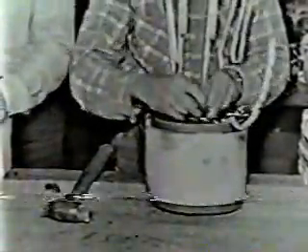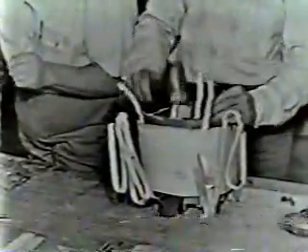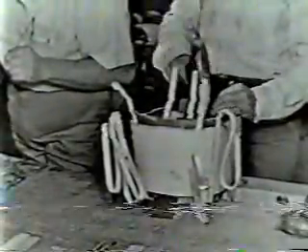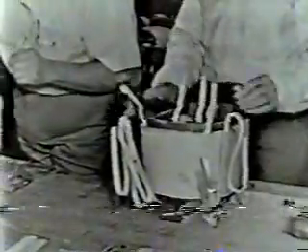Well, those 3 coils are loose now, but as I showed you these pieces of insulation, you see that man picking up one of those spacers. He is now getting ready to insert it between these coils so that the coils are equally spaced, and it also at the same time allows oil to flow between the coils to help radiate the heat while it's in service. There are still quite a few leads coming off of this coil. Will some of those be connected within the body of the coil itself? Yes, Bob.